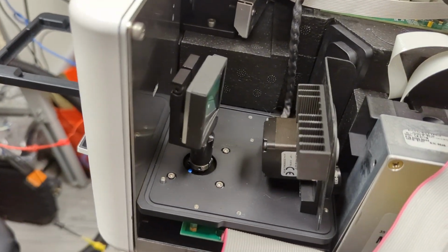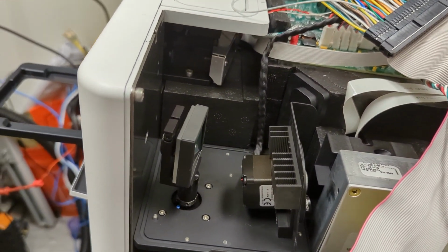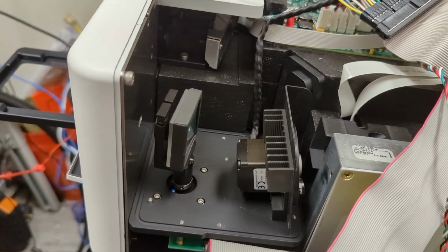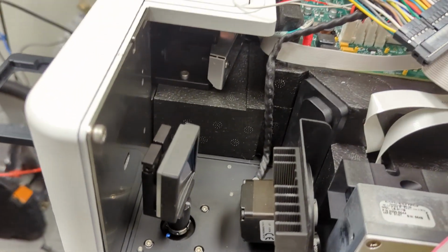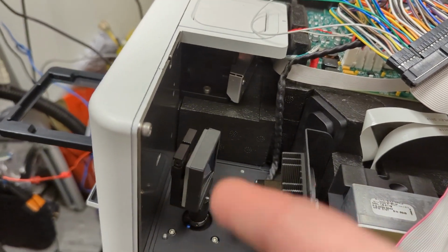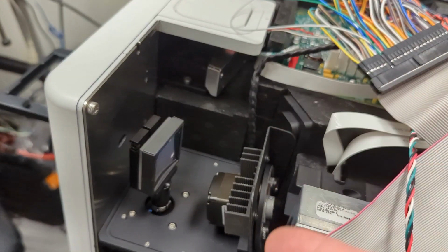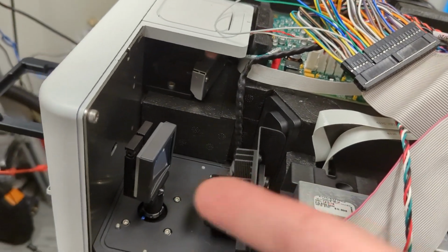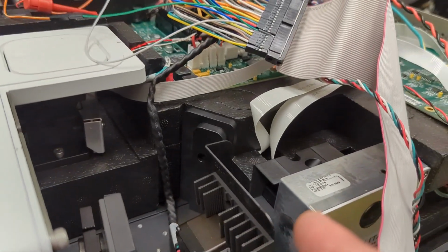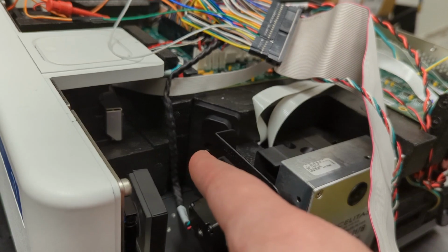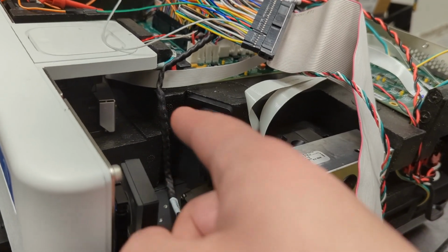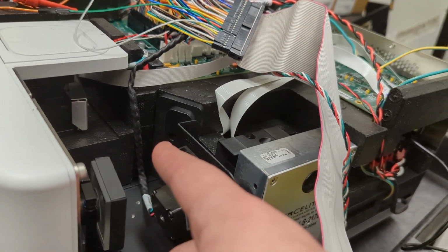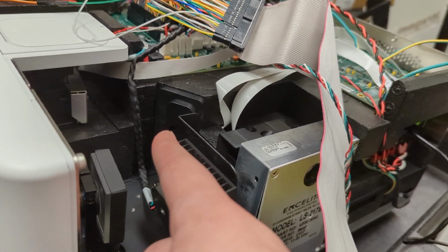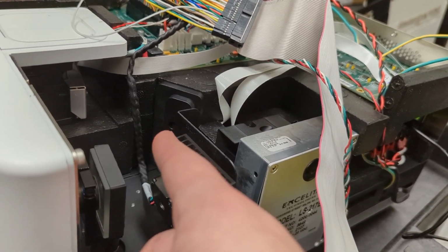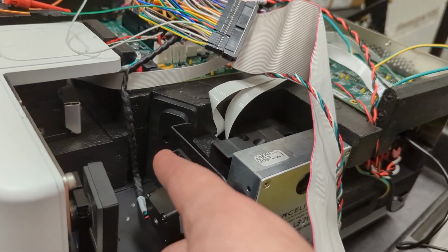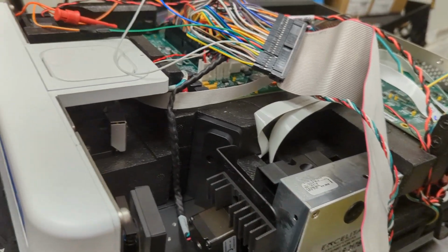Alright, so when this thing does its power on process, it spins this filter wheel. Well, it'll home this first, and then the lamp will come on briefly, and it'll spin the filter wheel to check that, and then there's one last step where it'll start moving slowly. You can see the zero order. I'm going to show this in a second, but you can see that it moves the zero order light to where the fiber optic cable is, and then from there it'll move it back and forth. So you can see it doing that self-calibration.